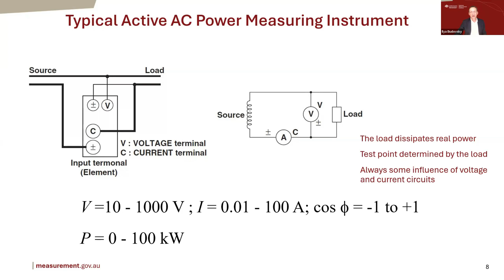And without exception now, the standards are organized in a phantom power configuration. So there is a so-called phantom power source, which is two separate sources, one for voltage and one for current. And then the voltage and current circuits of the IUT, the instrument under test, are disconnected. Then we need to convert the voltage of the IUT typically to a smaller voltage or a smaller current that we can measure, and we convert the current of the IUT into a smaller voltage or a smaller current again, and then we use a low-level power comparator to compare it usually with DC that we know in terms of quantum standards.